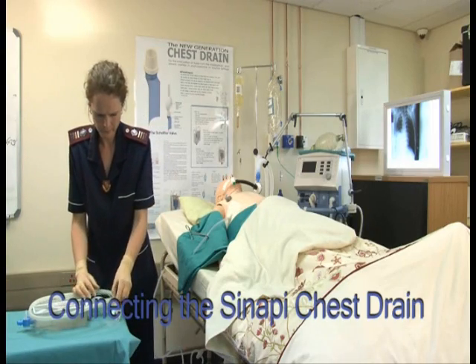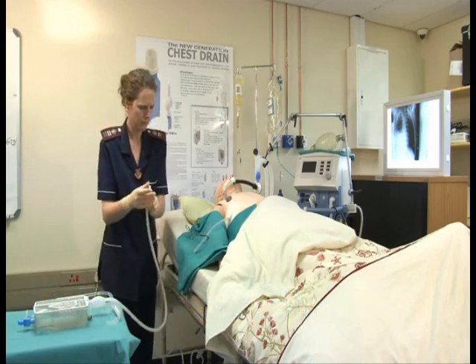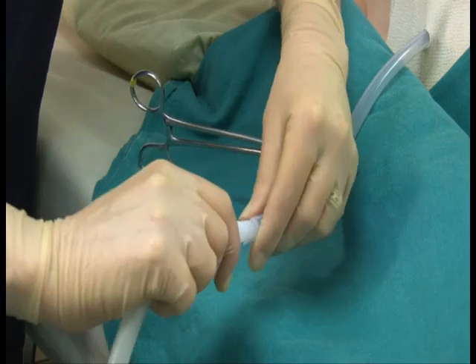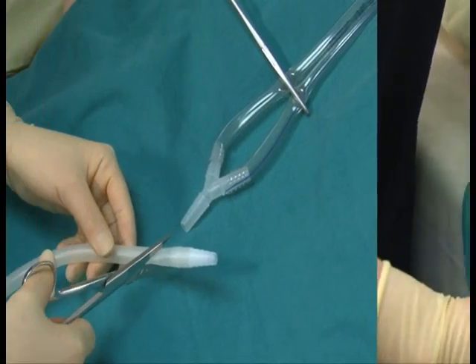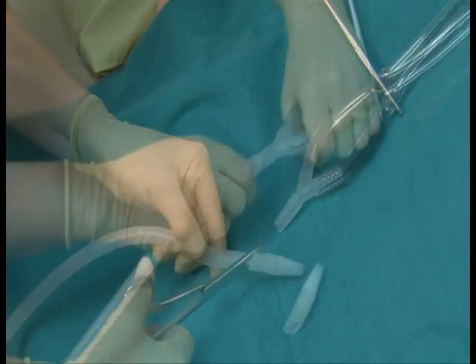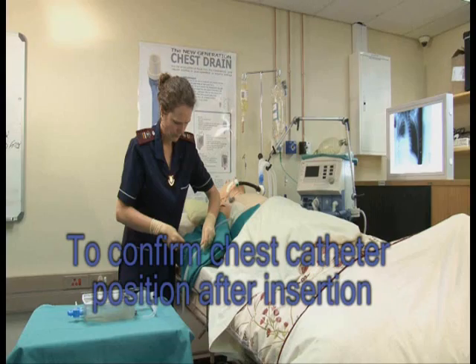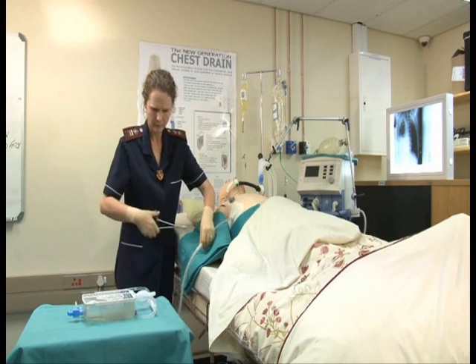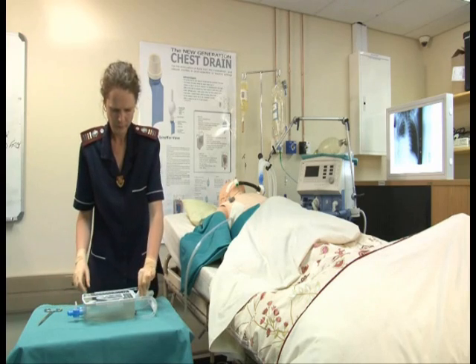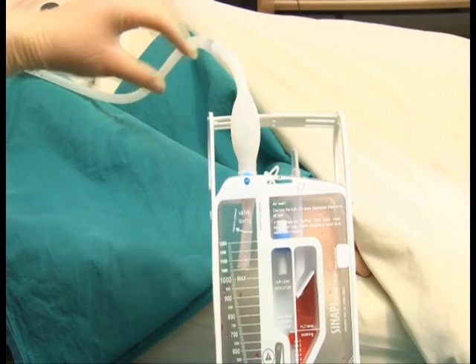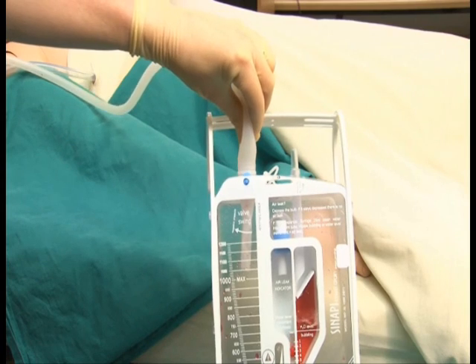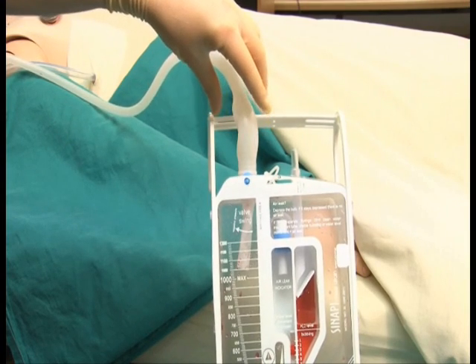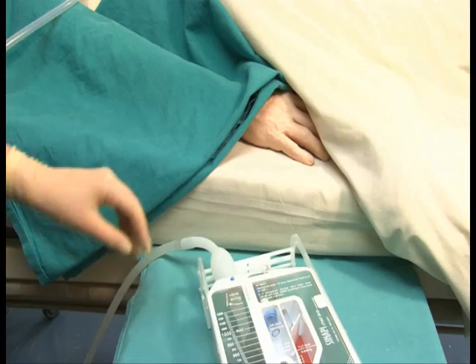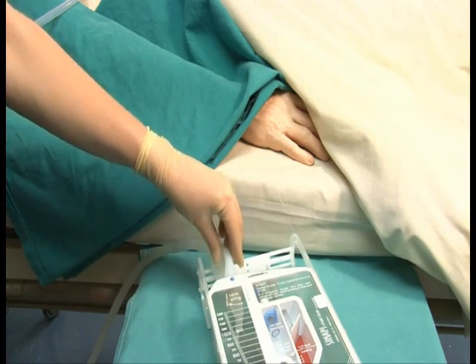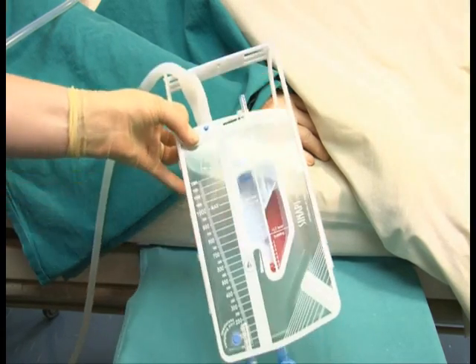Connecting the Sinapi chest drain. Open the pack and connect the connector to the chest catheter, ensuring a tight and secure fit. If required, use a Y connector to connect 2 chest catheters to 1 unit. To confirm chest catheter position after insertion, as soon as the catheter is positioned in the chest, depress the bulb. The bulb must initially re-expand, confirming that air or fluid is draining from the pleural space. If it does not initially re-expand, there is an absence of air or fluids at the catheter tip, and the catheter must be repositioned.